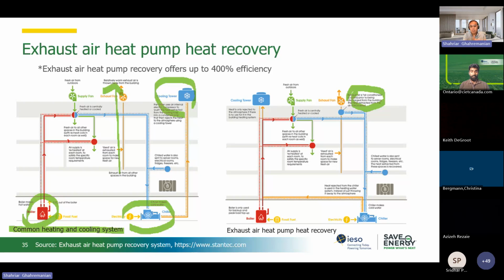This is a typical example for a building that has a data center, and the data center needs to run 24/7, it doesn't matter. Or if it's a hospital. So these are the examples for this application that I'm showing. And now it can send that cooled or conditioned refrigerant, I would say, back to the system that we have, and basically this is some kind of free cooling that we got. Yeah, my question is that: we are recovering the heat, how is it used for cooling here in the chiller? It's not going directly to the chiller, it's going to the distribution.